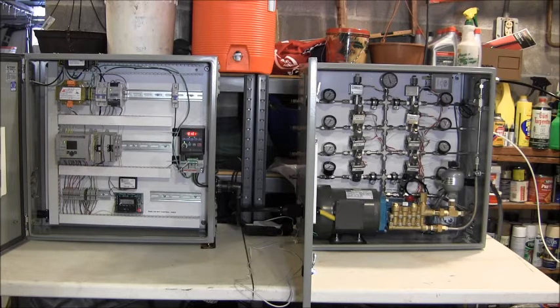And the motor itself is a 1/3 horsepower 3-phase motor. So with the 3-phase motor, you have the ability to vary the frequency, to vary the output capacity of the pump. Now that 3-phase motor is being driven by this variable frequency drive in the control panel on the left here. This is an Allen Bradley half horsepower 3-phase variable frequency drive, and it is supplying this motor through this cable assembly.